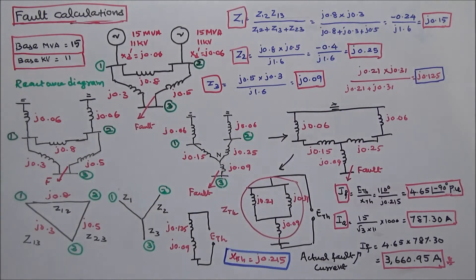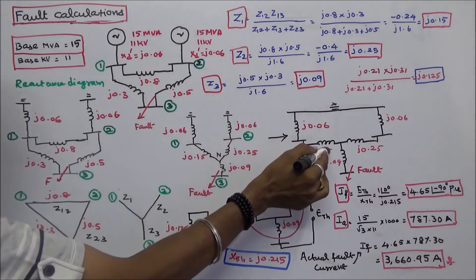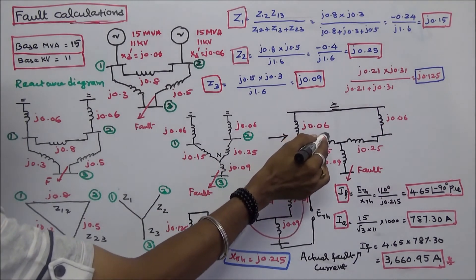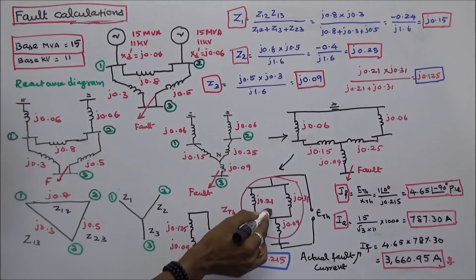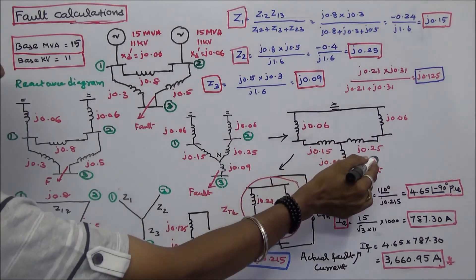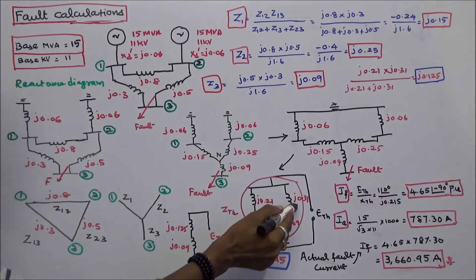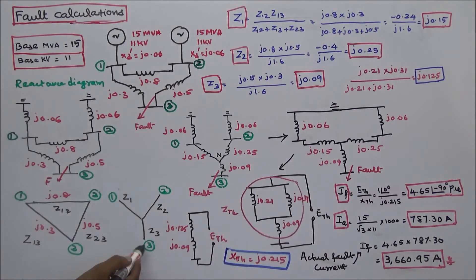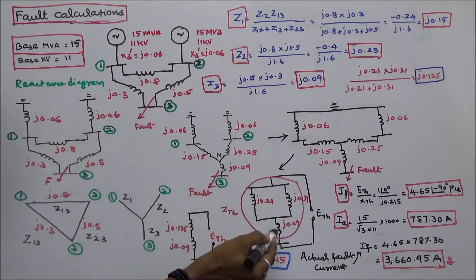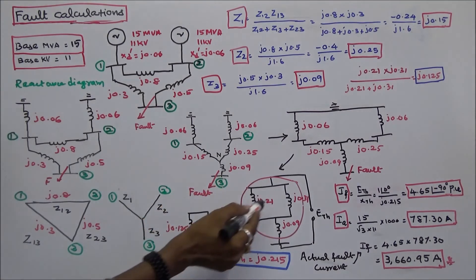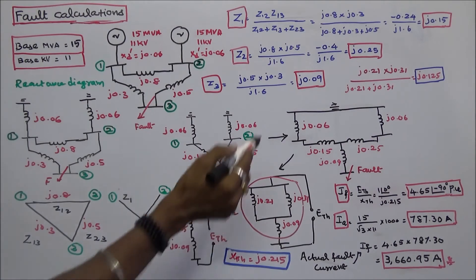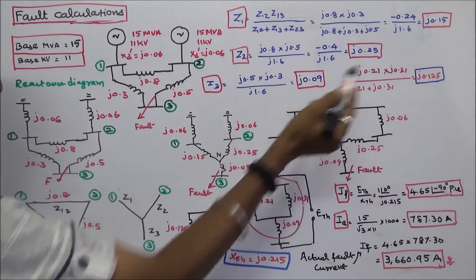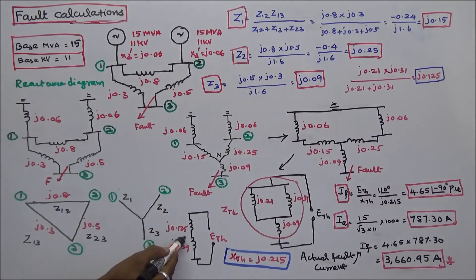Redrawing the circuit again, the generator reactances and star impedances in each branch are in series. J0.15 plus J0.06 equals J0.21, and J0.25 plus J0.06 equals J0.31. The Z3 branch remains J0.09. These two series branches — J0.21 and J0.31 — are now in parallel: J0.21 multiplied by J0.31, divided by J0.21 plus J0.31, equals J0.125.